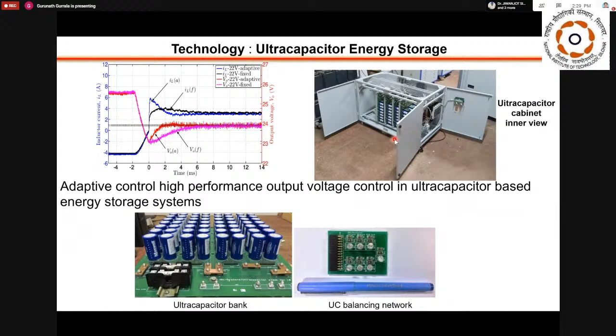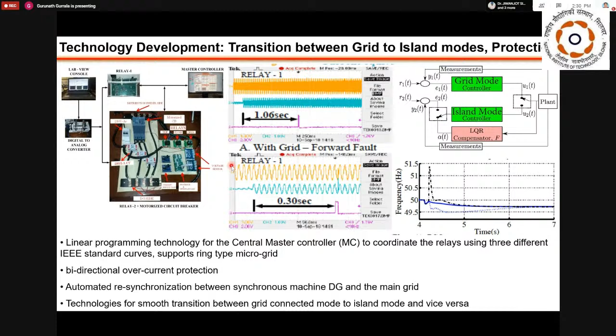The most important thing is connecting to the grid as well as disconnecting from the grid, and detecting islanding. These are the most important things as far as the microgrid is concerned. So we developed a custom platform which allows you to seamlessly synchronize to and disconnect from the grid without any jumps in the system's response. We developed controls for transitioning from islanded to grid mode and grid to island mode, and a lot of work has been published in this area.